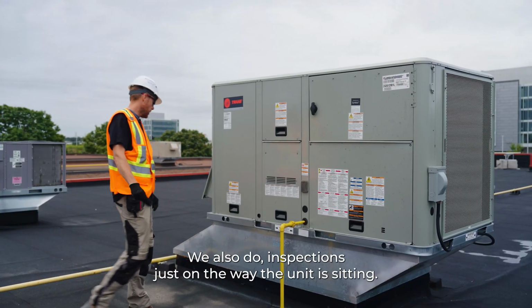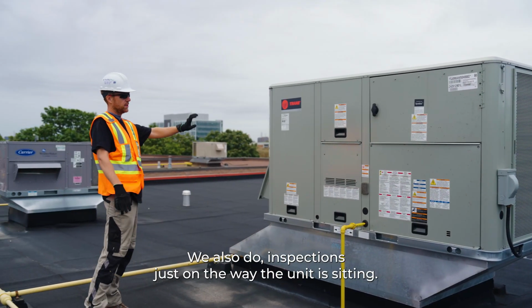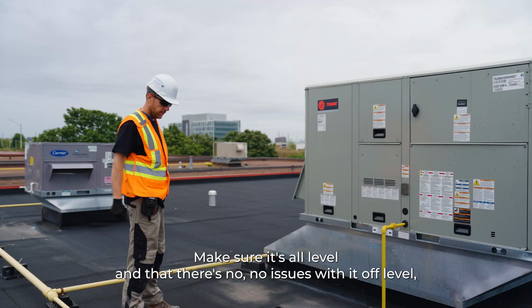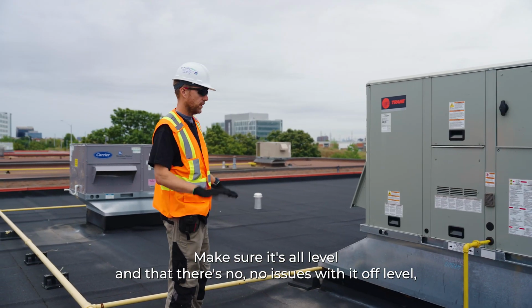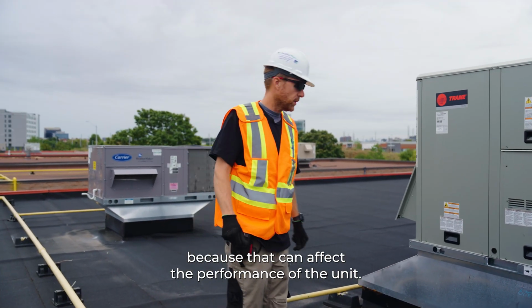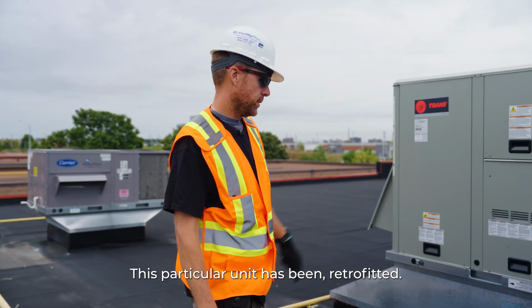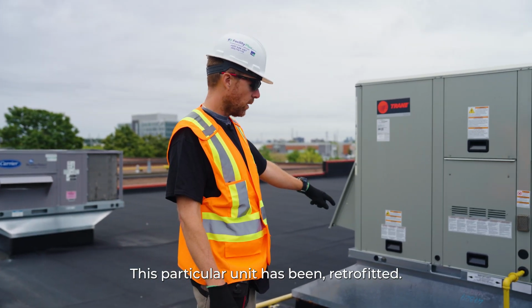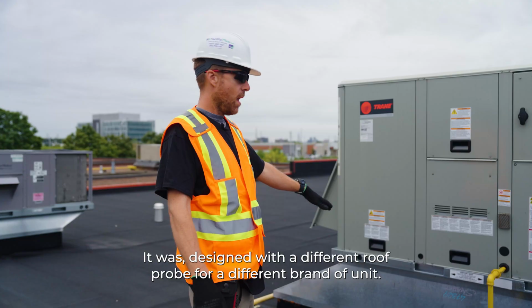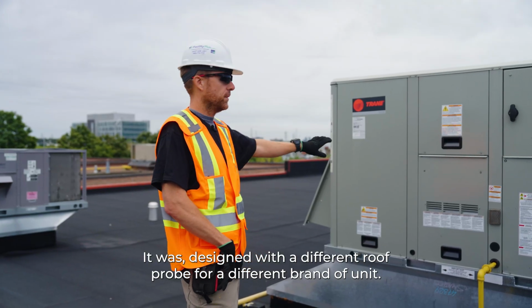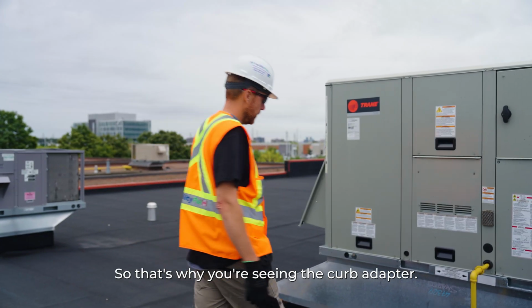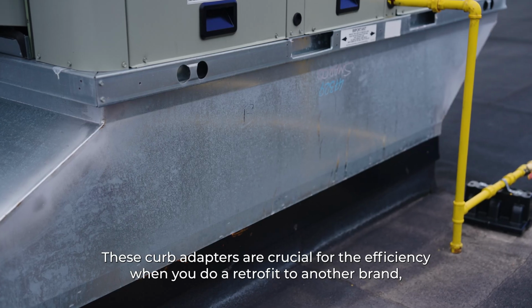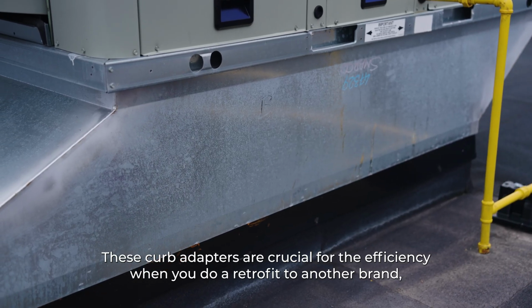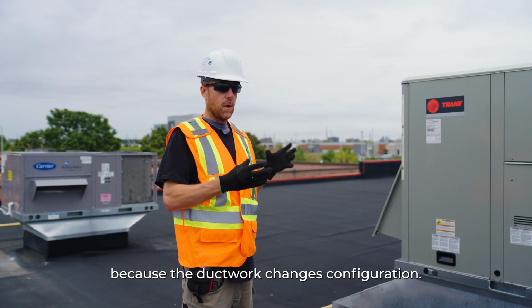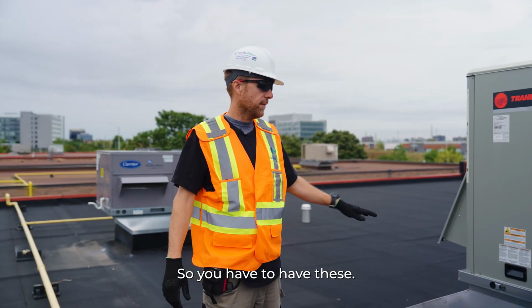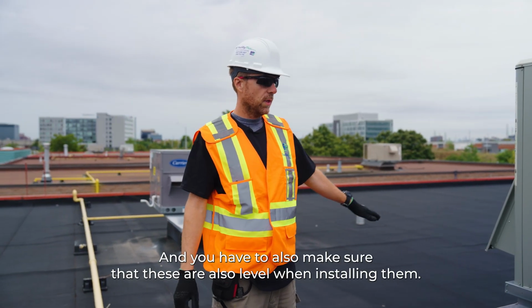We also do inspections just on the way the unit is sitting. Make sure it's all level and that there's no issues with it being off level, because that can affect the performance of the unit. This particular unit has been retrofitted. It was designed with a different roof curb for a different brand of unit. So that's why you're seeing the curb adapter. These curb adapters are crucial for the efficiency when you do retrofit to another brand, because the ductwork changes configuration. So you have to have these. And you also have to make sure that these are level when installing them.